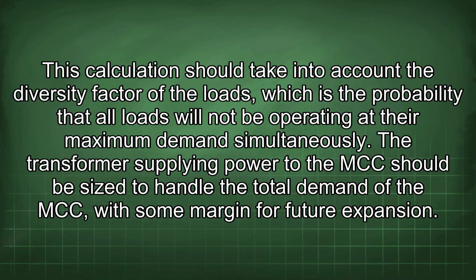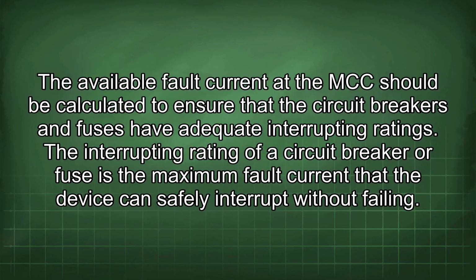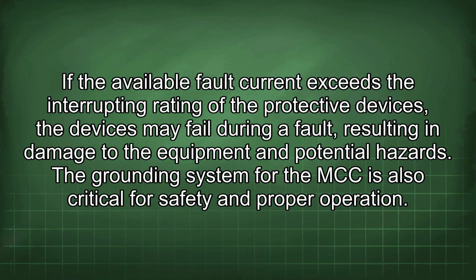The transformer supplying power to the MCC should be sized to handle the total demand of the MCC with some margin for future expansion. The available fault current at the MCC should be calculated to ensure that the circuit breakers and fuses have adequate interrupting ratings. The interrupting rating of a circuit breaker or fuse is the maximum fault current that the device can safely interrupt without failing. If the available fault current exceeds the interrupting rating of the protective devices, the devices may fail during a fault, resulting in damage to the equipment and potential hazard.